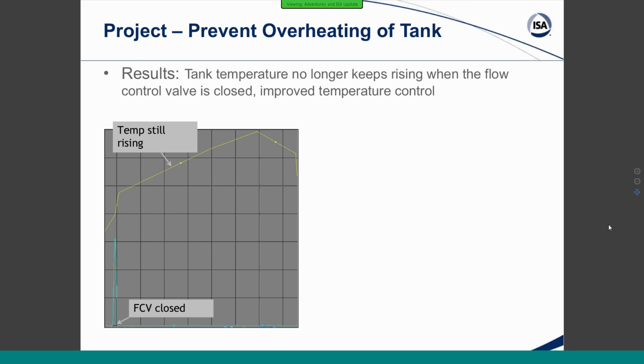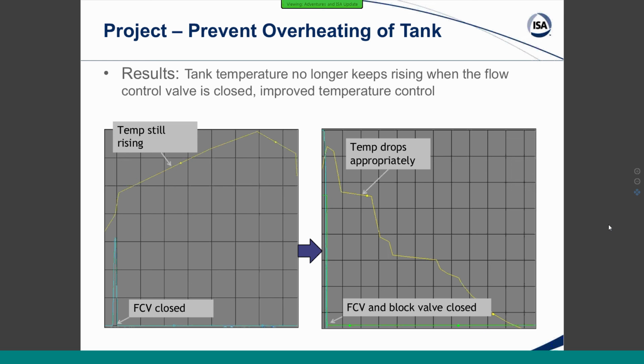Okay, so results were good. Our temperature is no longer rising. You can see on this first chart here that the flow controller is closing. This is prior to putting the block valve on there, but the tank temperature is still rising independently of that because of the steam leak. Once we put the block valve on, the control valve closes, which causes the block valve to close, and our tank temperature starts to drop like it should, just due to all of the natural heat losses.